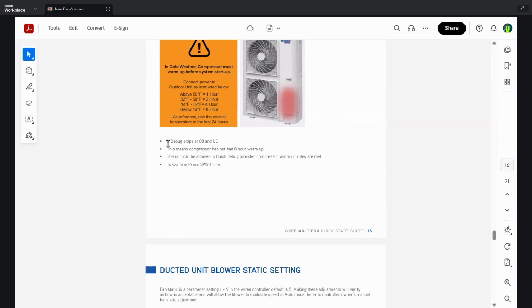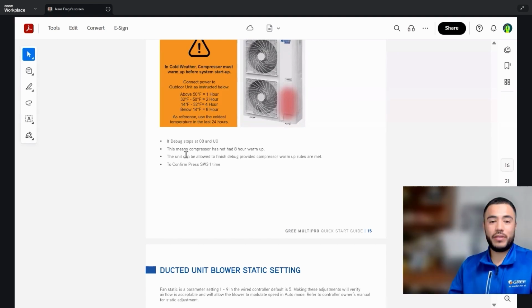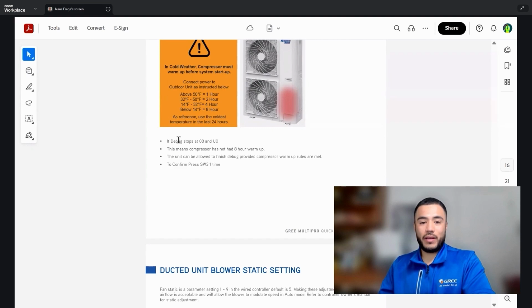You'll notice during debug, this, along with a couple of other steps, will actually stop, and it will not continue unless you manually confirm whether the value that the control board is receiving is correct or not. So if we stop at debug 08 and UO, this means the compressor warm-up period. And if you have already followed these steps, you can go ahead and hit SW3, and it'll continue on its course to doing the debug.